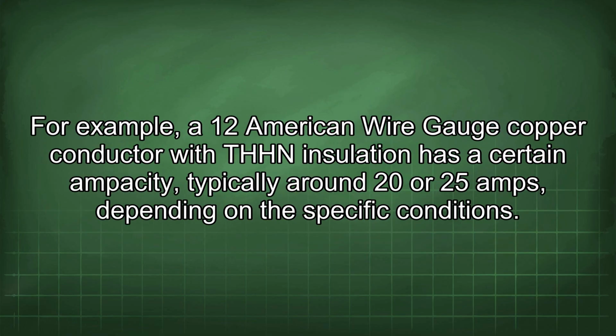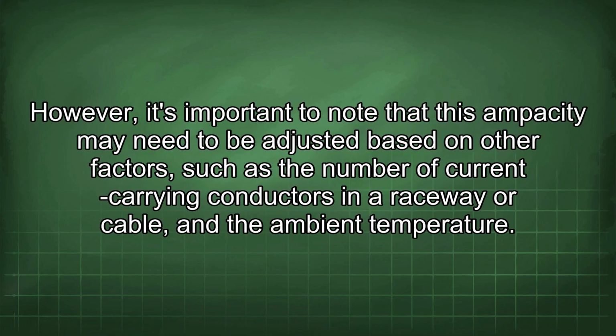For example, a 12 American wire gauge copper conductor with THHN insulation has a certain ampacity, typically around 20 or 25 amps, depending on the specific conditions. However, it's important to note that this ampacity may need to be adjusted based on other factors, such as the number of current-carrying conductors in a raceway or cable, and the ambient temperature.